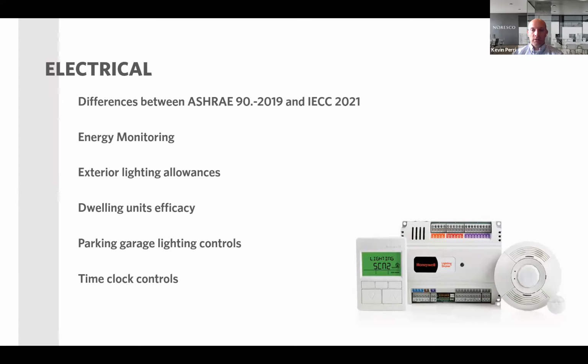For ASHRAE, the categories are total electrical energy, HVAC, interior lighting, exterior lighting, and receptacle loads. So still 5 categories, but they're just broken out differently. It's the same requirement in terms of square footage for ASHRAE as it is for IECC, where any buildings over 25,000 square feet are required to monitor their energy. However, the differences are tenant spaces. ASHRAE addresses tenant spaces. So any tenant spaces that obtain more than 10,000 square feet, that's not in a residential unit, then it has to be monitored separately, and that has to go to the tenant as well. They have to be able to see those reports.